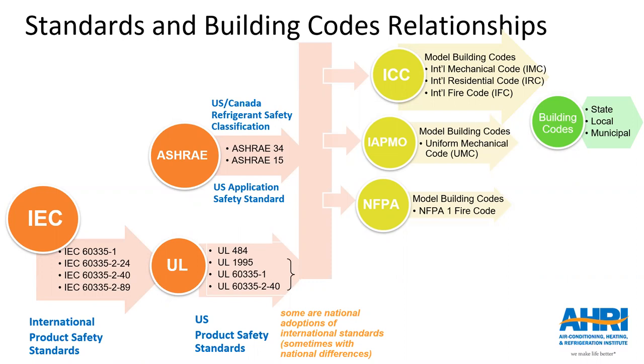So primarily the building codes reference these product safety standards, and building codes also require the use and installation of listed products, as I described earlier. Also, once the model building codes are determined, they get considered to be adopted by the state, local, and/or municipal authorities, which once accepted become law of that jurisdiction. So all in all, this is a good representation of how a safety requirement traverses from an international standard, the IEC standard, all the way to our local jurisdictions and becomes law of that jurisdiction in the U.S. Next slide.